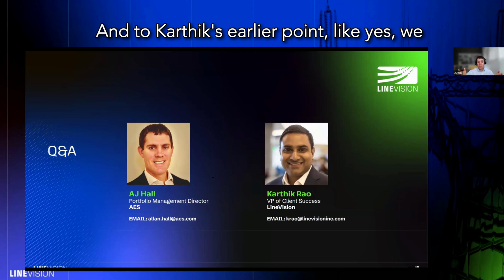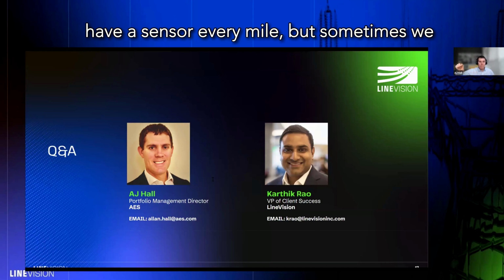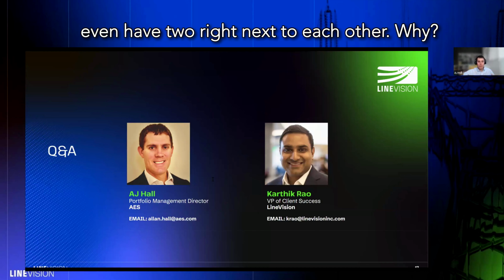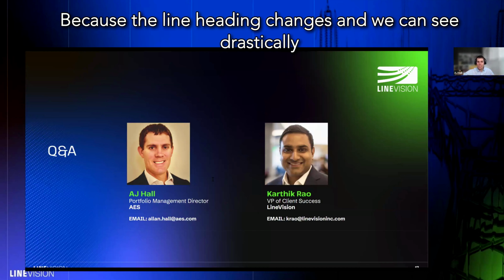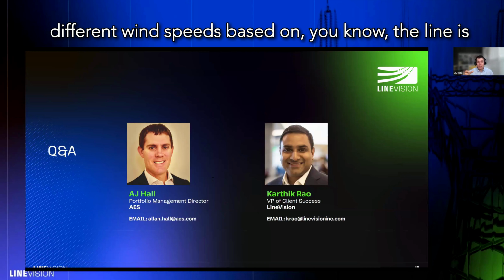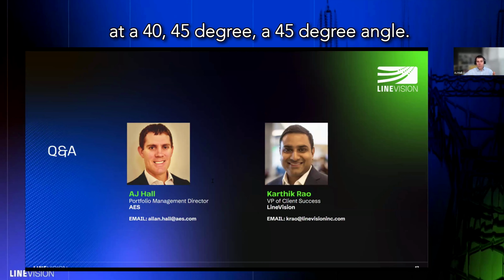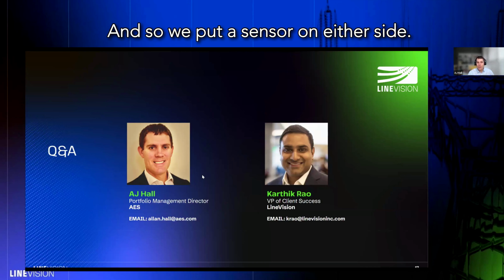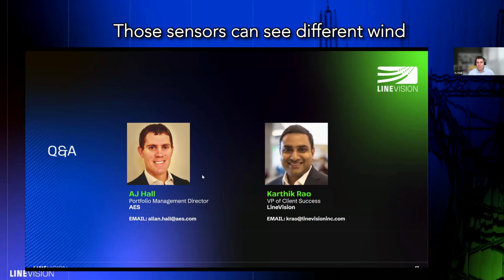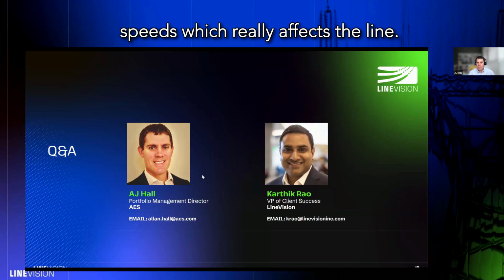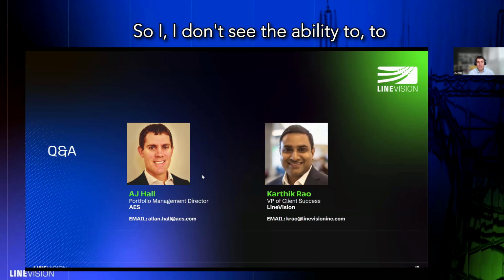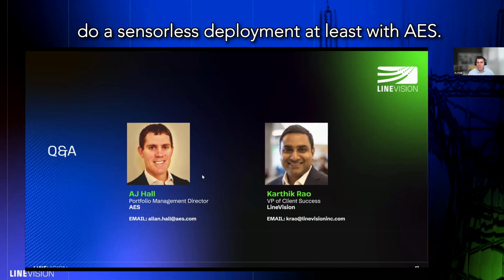To Karthik's earlier point, yes, we have a sensor roughly every mile, but sometimes we even have two right next to each other, because the line heading changes. We can see drastically different wind speeds where the line is at a 45 degree angle, so we put a sensor on either side, and those sensors can see different wind speeds, which really affects the line rating. So I don't see the ability to do a sensorless deployment, at least with AES.